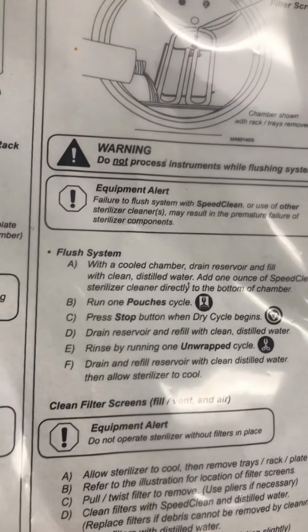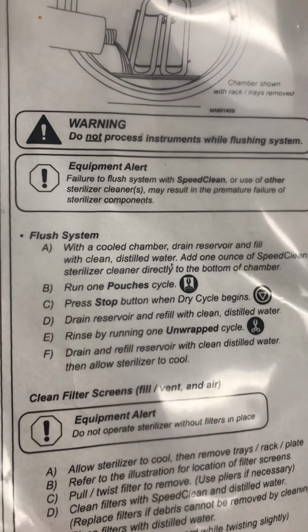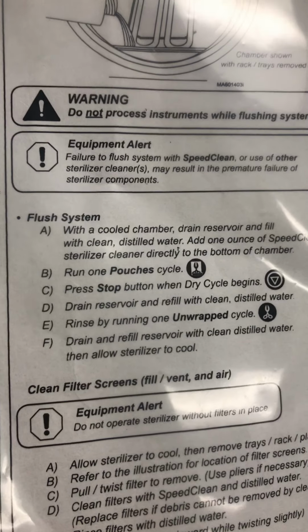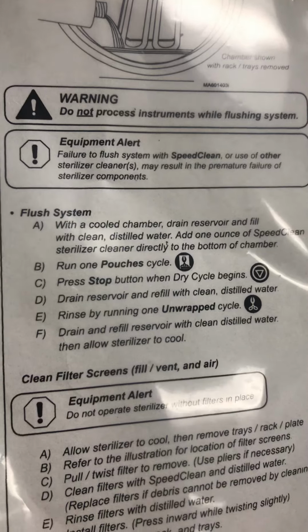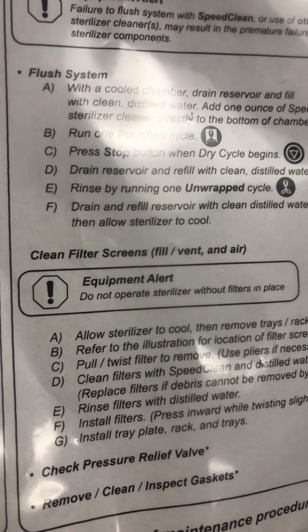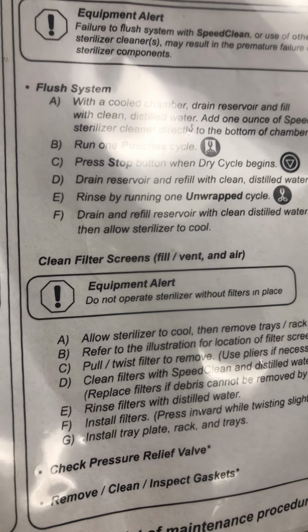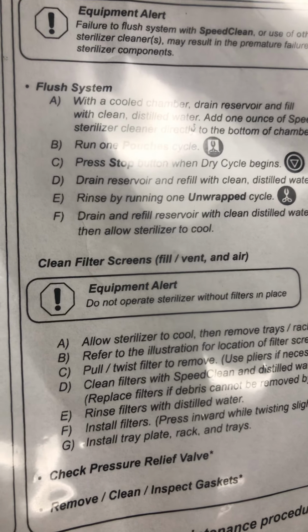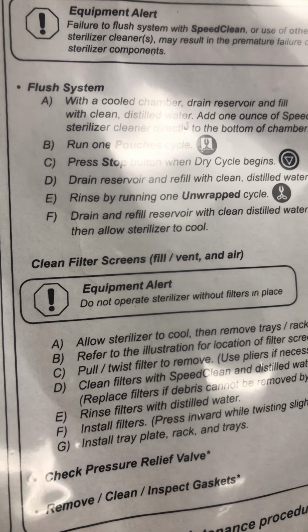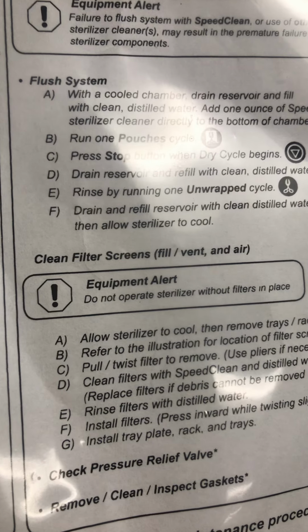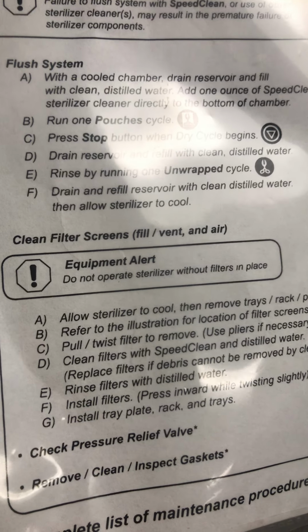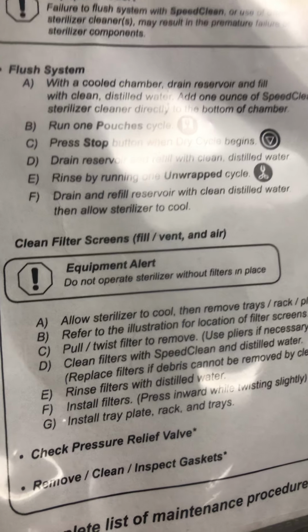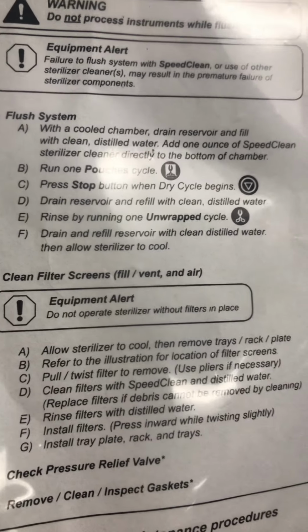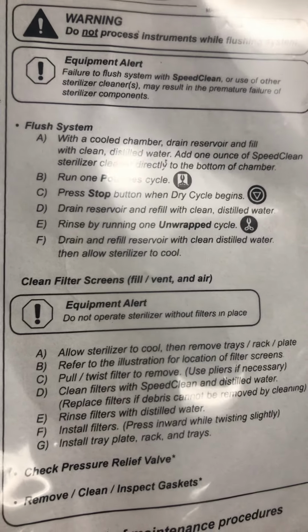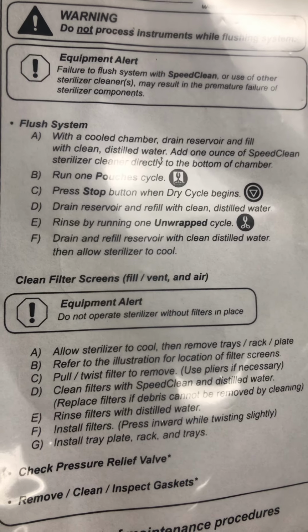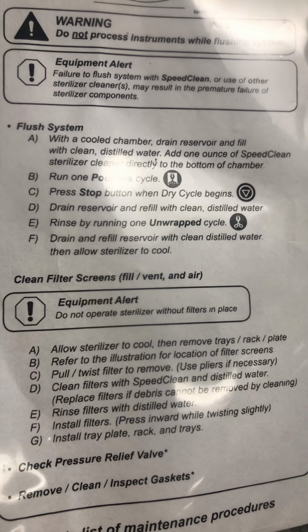And we also have monthly maintenance that we have to do, which is more intense. So this is basically, we're cleaning it out, wiping it out, removing all the shelves and the basket inside, and cleaning those out, removing the water, and refilling it with clean distilled water. So here is our manufacturer's recommendations for cleaning our autoclave, just for your information. So you'll be doing that as well.